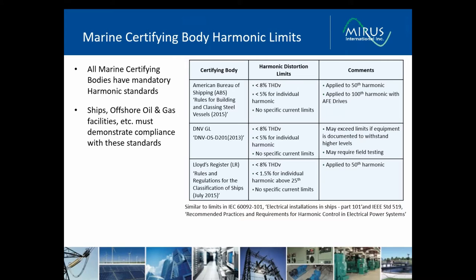As mentioned earlier, all marine certifying bodies have mandatory harmonic limits. Here we're showing some notes from three of the more important ones, ABS, DNVGL, and Lloyd's Register. There are many more, and they all have similar requirements. All basically limit the voltage distortion to 8%, with harmonics up to the 50th. ABS, it's important to note, applies harmonics up to the 100th when active front-end drives are being used. This is because of the higher frequency harmonics that these AFE drives generate. I'll expand on that later in the presentation today. And there are no specific limits for current distortion. Current distortion is indirectly limited, however, because the harmonic currents must be reduced in order to meet the voltage distortion limit.